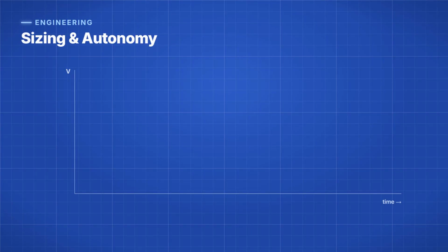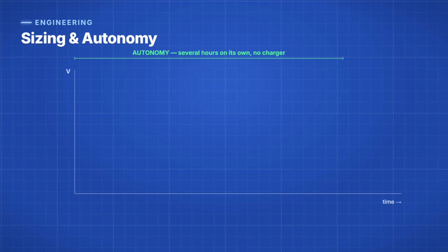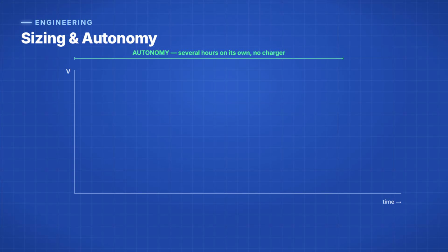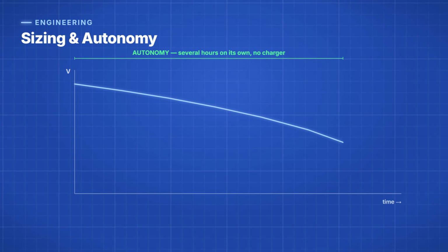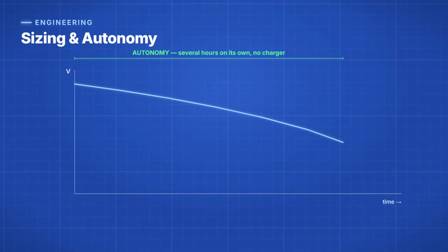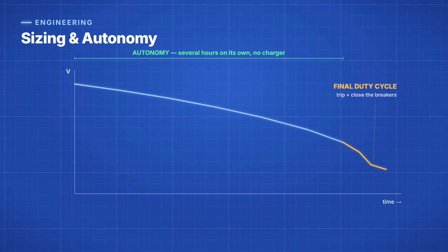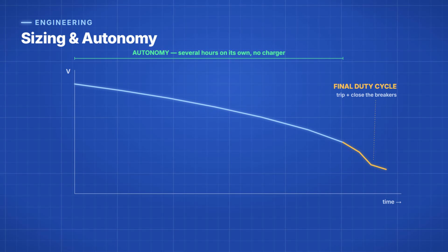So, how big does the battery bank need to be? It's sized for a number called autonomy, which is how long it must run the whole DC load on its own, with no charger at all. Often, that's several hours. Enough time for an operator to find and fix the supply problem. On top of that standing load, the bank must keep enough in reserve for the final duty cycle, which is the burst of energy to trip and close breakers right at the end.